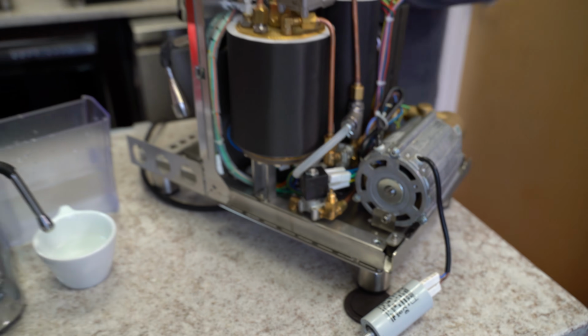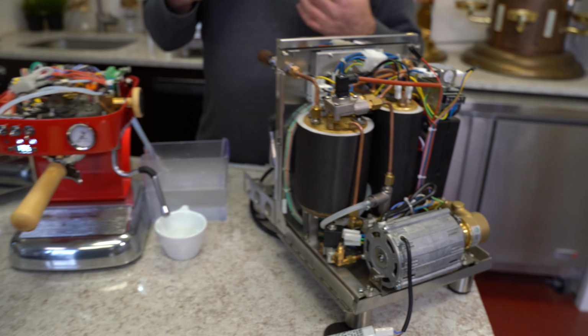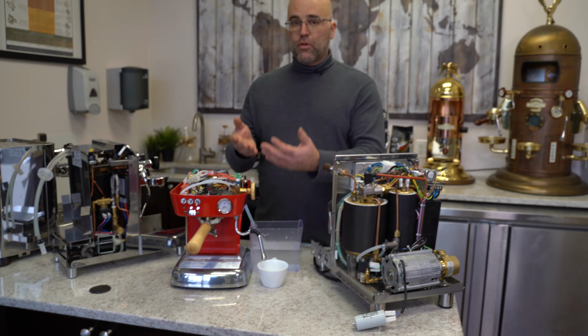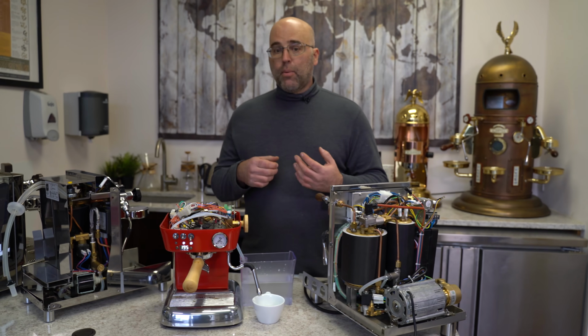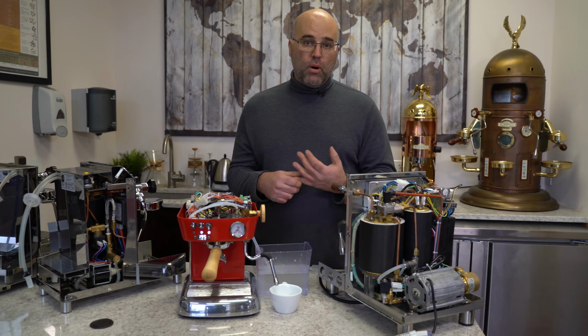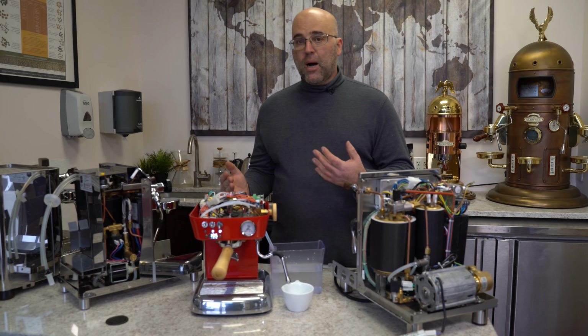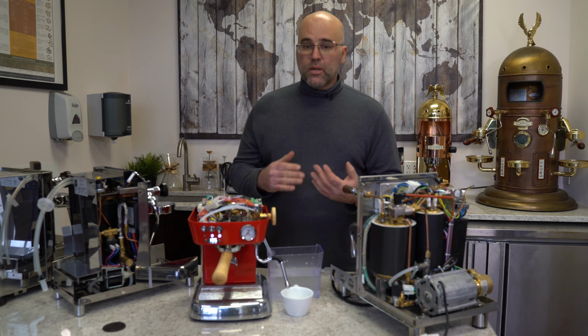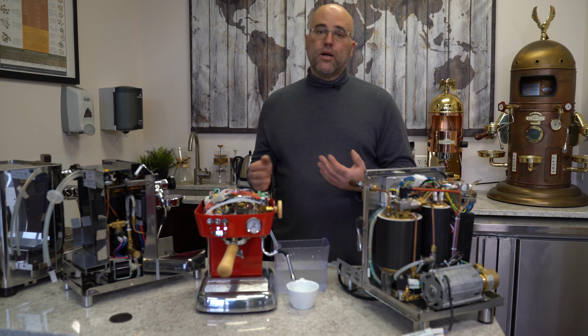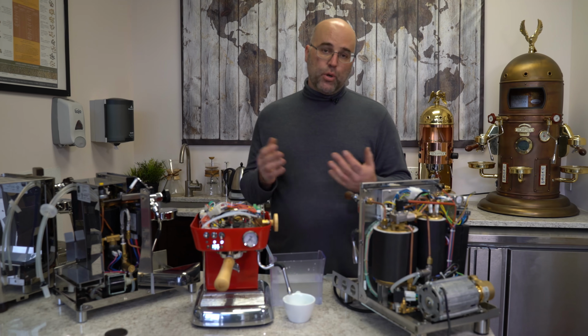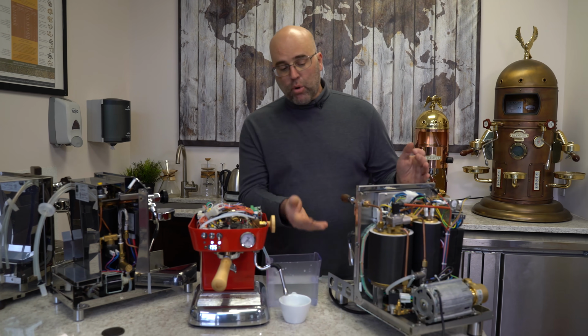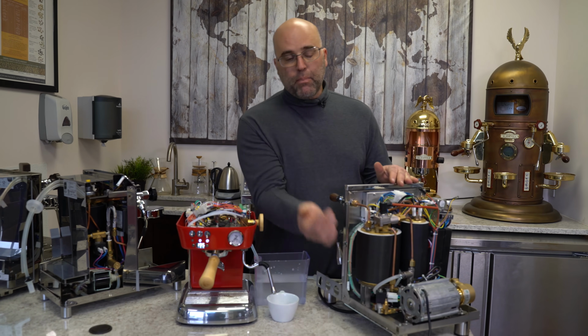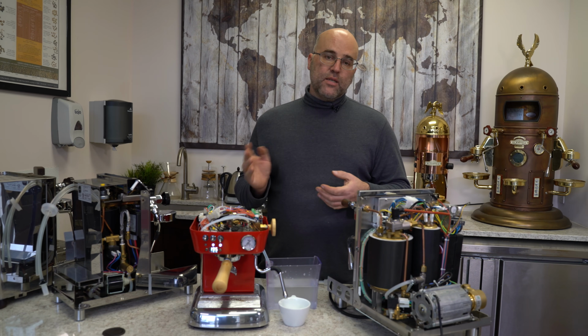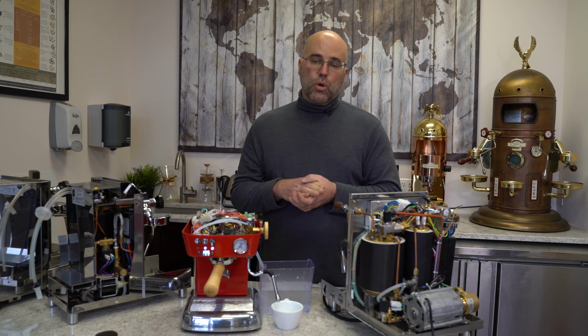So those are the different areas to check when you don't have any water going through the pump and through the machine. Number one is to try to manually prime it to remove the air pocket and get that out. Next stage would be to check the wiring on the inside with our assistance if you purchase from us. And again, on a rotary vane, you would just turn that bolt or screw there clockwise and counterclockwise, approximately 2 turns each.